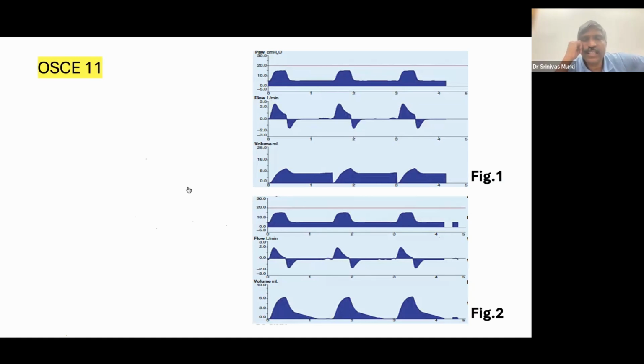So what part of synchronization will it help? I think nobody has been able to answer it so far. Not auto triggering. It will not trigger. If you have a leak, triggering will not happen. So leak adaptation will allow triggering. What will you do?